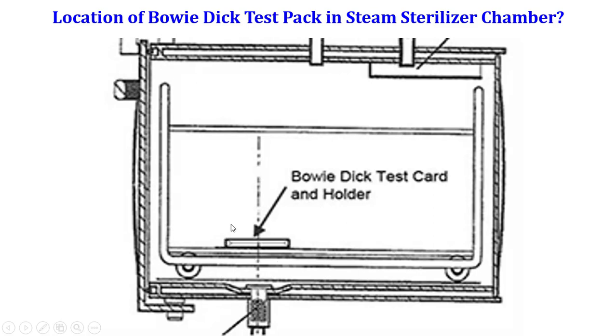The Bowie-Dick test pack is placed in the chamber on the trolley, close to the drain. The drain is located at the bottom of the chamber, and the Bowie-Dick test pack is placed just over the drain — this is the correct location for the Bowie-Dick test pack.